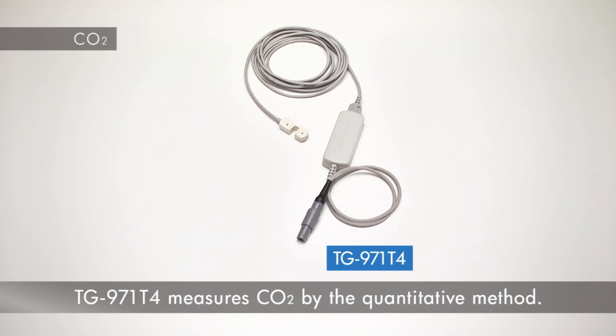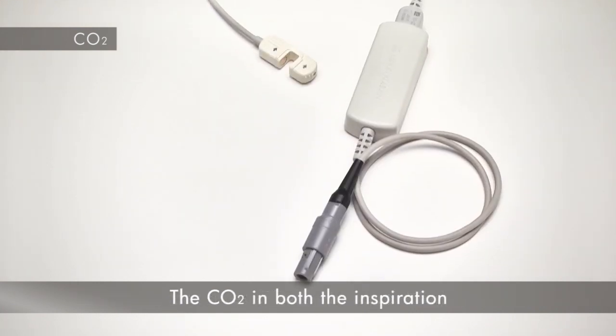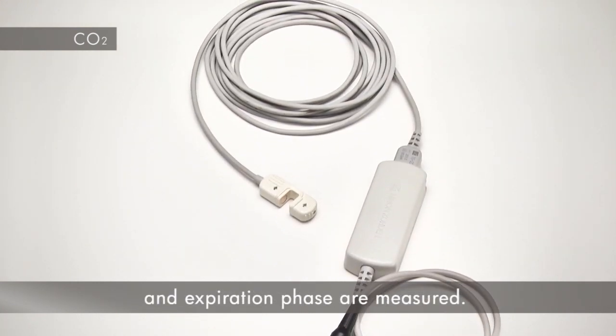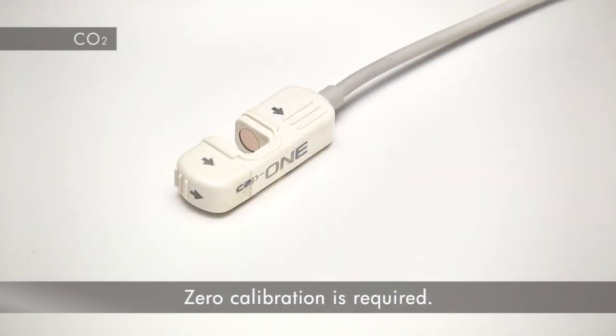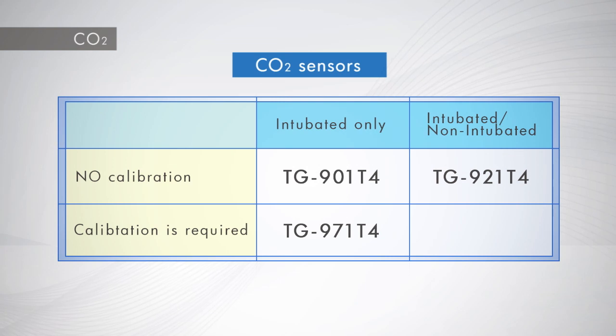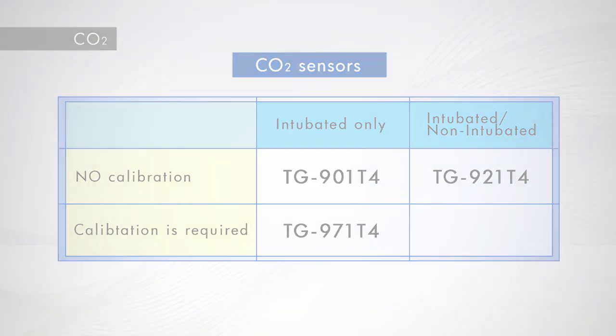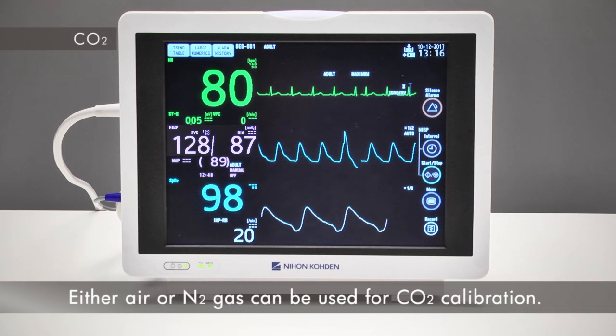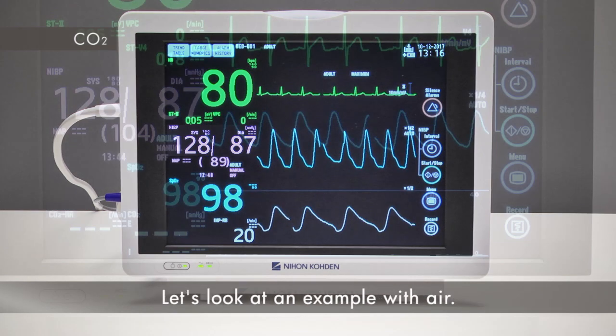TG971T4 measures CO2 by the quantitative method. The CO2 in both the inspiration and expiration phase are measured. Zero calibration is required. Either air or N2 gas can be used for CO2 calibration. Let's look at an example with air.